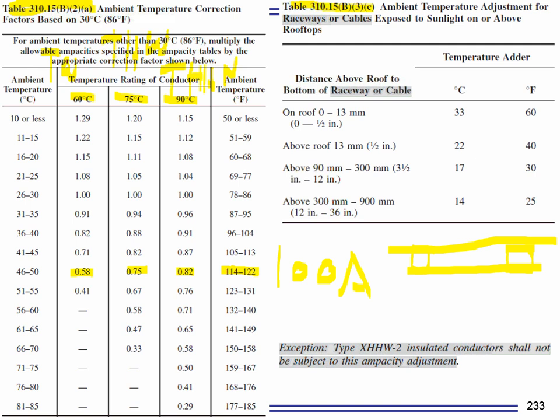Okay, let's just say you decided to put a block that raises your conduit on a roof up to say 3.5. Say four. Let's just say a 4 inch block. We put it there, and then you take your ambient temperature of 30 degrees. So if you're in Minneapolis, ambient temperature 90. For derating purposes, now you add a 30 to it. It becomes what? Now it becomes 120. They call it a temperature adder. It becomes 120.